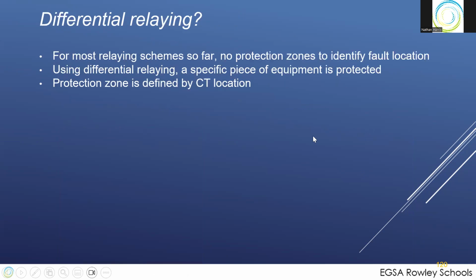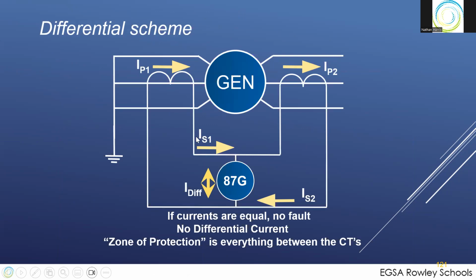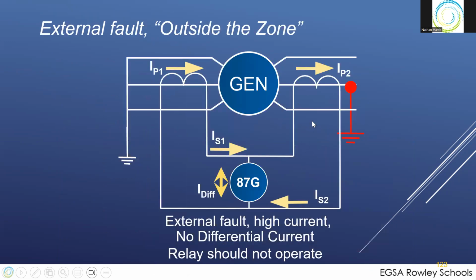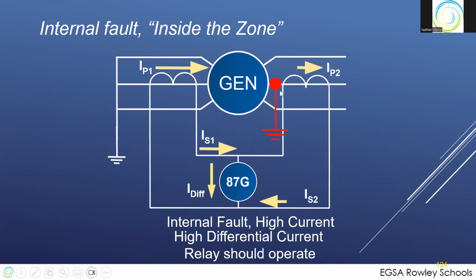Differential relaying, it's a zone of protection. If you have current, it balances the current this side and that side. If they're equal, it doesn't trip. If you get a fault outside, it won't trip. So a fault out here, no trip, because the current here equals the current there. If you have a fault here, it will trip because this current does not equal that current. All right, so that's what a differential relay does.